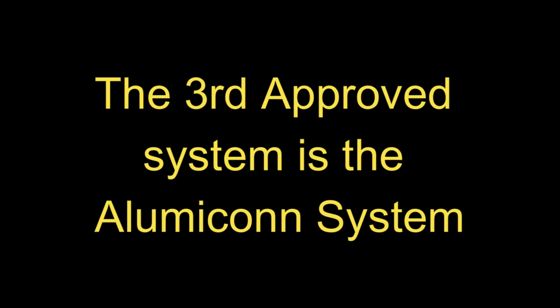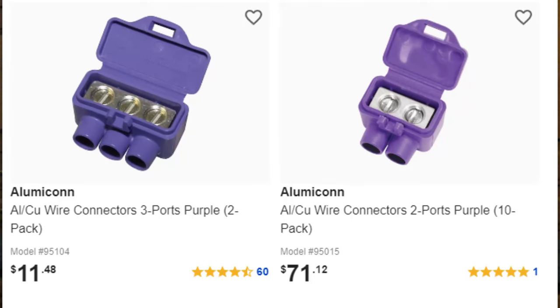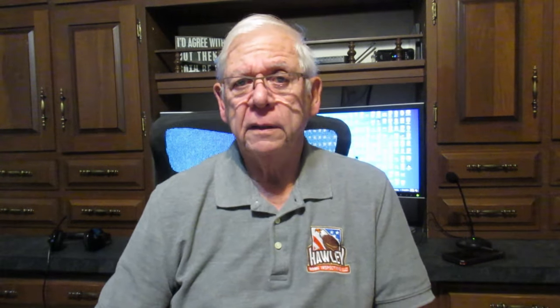The third approved system, the Alumiconn — as you can see above — is basically a splice block. You put the aluminum wire in and tighten one screw down on it, then put the copper pigtail wire in on the other side and screw it down. The reason we do this is that most of the receptacles and switches in use now are not rated for use on aluminum wire. The Consumer Product Safety Commission recommends these three procedures only for correcting aluminum wiring.